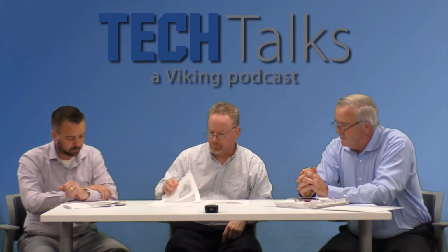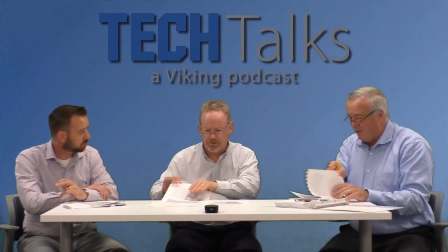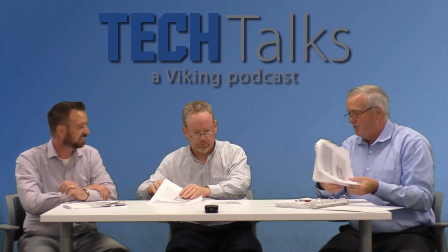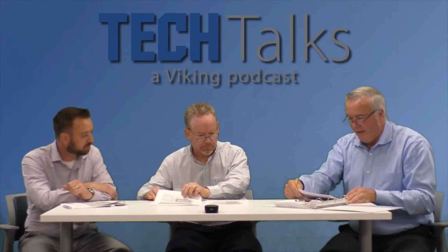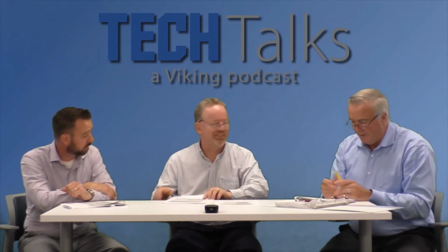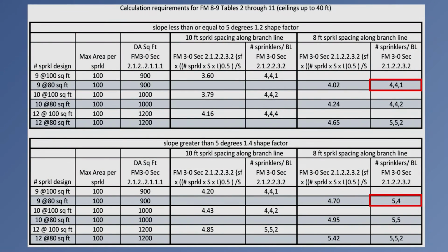Actually, let me start with the table again, because I started the last one with the table of selection. Table 6 that you're looking at is now applying to tables 2 through 11. And this table uses the FM 3.0 for the shape factor for the hydraulic area. So if you have a 9 or a 10 or even a 12, you have to go to 3.0 if you're in tables 2 through 11. You don't get the exception that table 17B has.